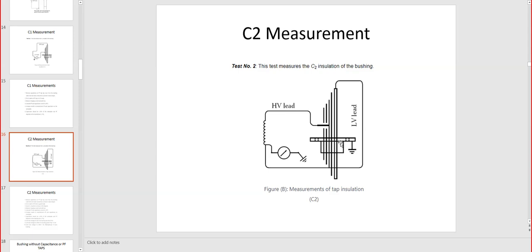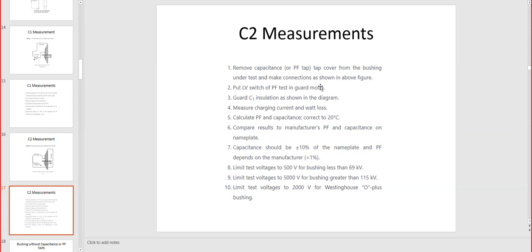Measurement for the C2, right? The C2 test. Now we connect the instrumentation on the tap, and then we make the connection of the instrument to the ground with the tap grounded. Now we measure the other side of the tap, from the actual hot collar tap connection to the ground, so the other remaining side of the bushing. For C2 we have similar instructions, and I will not read them all. They are here, similar instructions saying again that 20 degrees Celsius needs to be corrected to the reading values. Changes of plus or minus 10% or more are not acceptable.